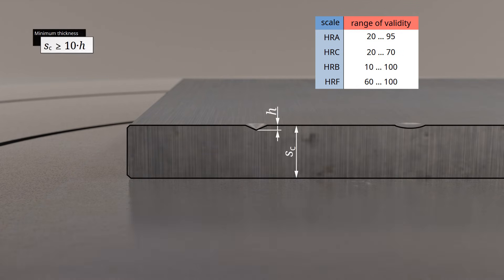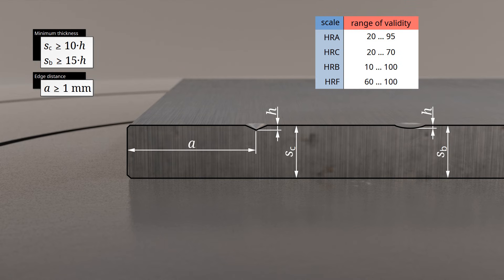A minimum sample thickness must also be ensured so that the result is not influenced by the support of the testing machine. For test variants with cone-shaped indenters, the minimum sample thickness corresponds to 10 times the permanent indentation depth. For scales using spherical indenters, the minimum sample thickness corresponds to 15 times the permanent indentation depth. In all cases, the distance of the indentation to the sample edge must be greater than one millimeter. The surface of the specimen must also be ground and must not exceed a mean roughness of 1.6 micrometers. Otherwise, the surface roughness would lead to large measurement uncertainties.